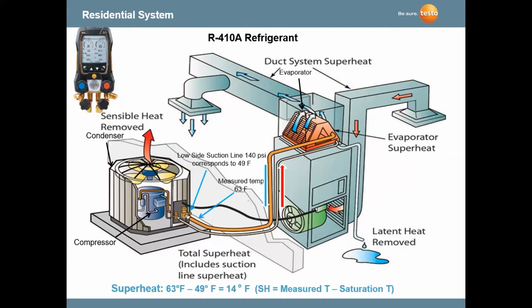Just put in the correct refrigerant, and there's over 90 different refrigerants in these instruments. So as you're charging the system, you're looking at superheat. It's doing the math for you based on the refrigerant that you select, the temperature measurement on your suction line, and the pressure that's on the suction line itself.